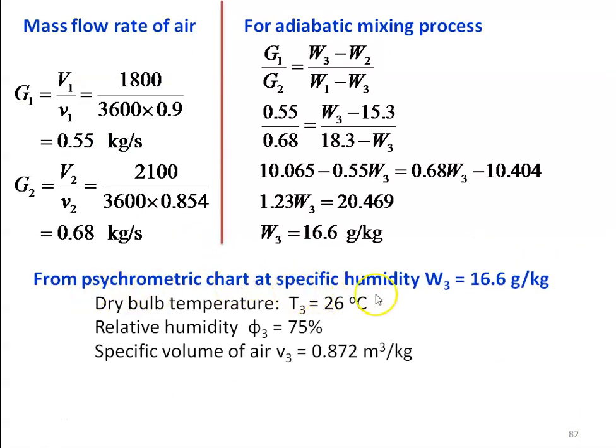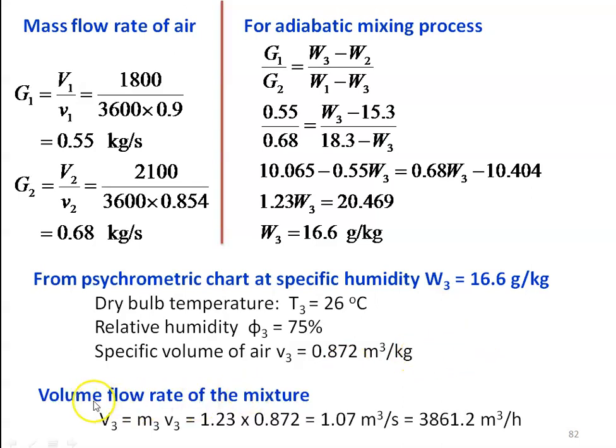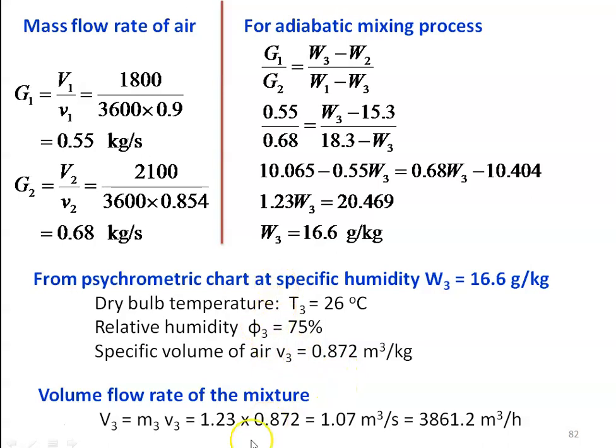From the psychrometric chart, at specific humidity W3 = 16.6 g/kg: dry bulb temperature is 26°C, relative humidity is 75%, and specific volume V3 = 0.872 m³/kg. The volume flow rate of the mixture V3 = M3 × v3. Total mass M3 = G1 + G2 = 1.23 kg/s. So V3 = 1.23 × 0.872 = 1.07 m³/s, or 3861.2 m³/hour. That is the volume flow rate. These are all the properties of the mixture — this is the answer to the problem.